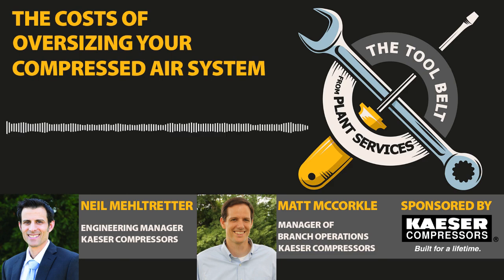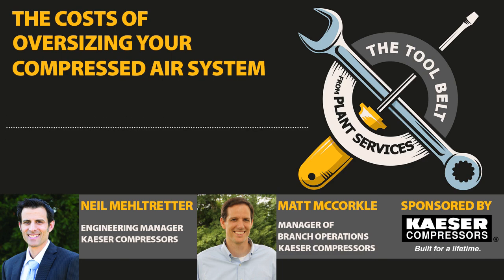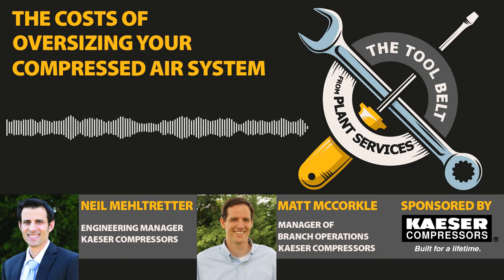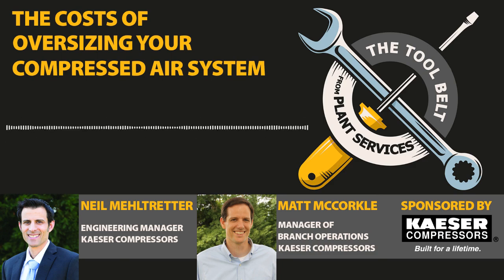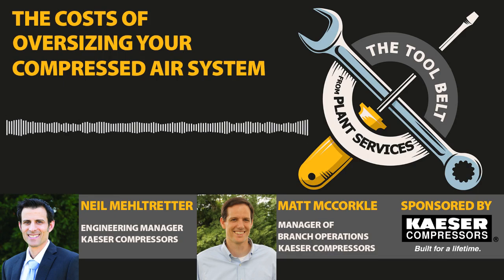Absolutely. So what we found is we analyzed 3 years of air study data. And on average, customers' compressed air systems are operating at 45% of capacity. So what that means is they have double the compressor capacity that they need to operate on average. And further confirming that 45% number, we've also seen studies done by other organizations that show a similar case, particularly for manufacturing.